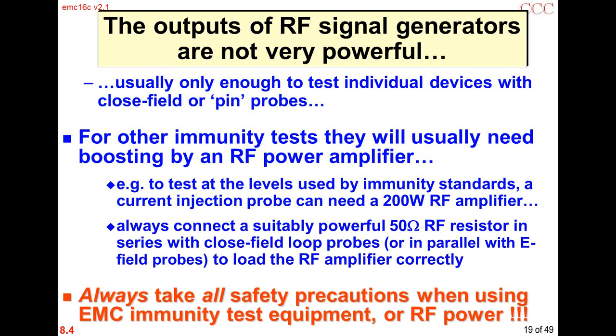Always take all safety precautions using any immunity test equipment or radio frequency power. Not many people realize that if you put a signal generator with an N-type output on a shelf at about eye level, and look at the center pin of the N-type connector from a foot or two away, if the signal generator is set to a high level and a microwave frequency, you can actually damage your eye. The N-type connector isn't a very efficient antenna, it's a very narrow beam, but if you're looking straight at it, your eye is right on that beam.